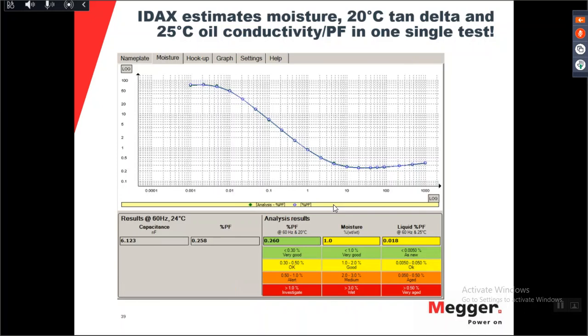temperature. There is a chart describing this, saying that at 40 degrees and 3,000 liters, cleaning the paper of a very large transformer takes about 1 year. If you use 200 liters and 20 degrees, it will take 30 years. So cleaning the oil will also help fix the paper, but it takes time. It takes months. So you cannot clean the oil in a few days or in 1 day. If you just do 1 day of oil purification, no, it will not fix the paper.